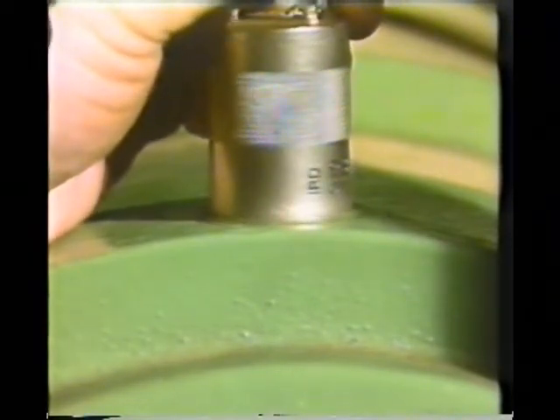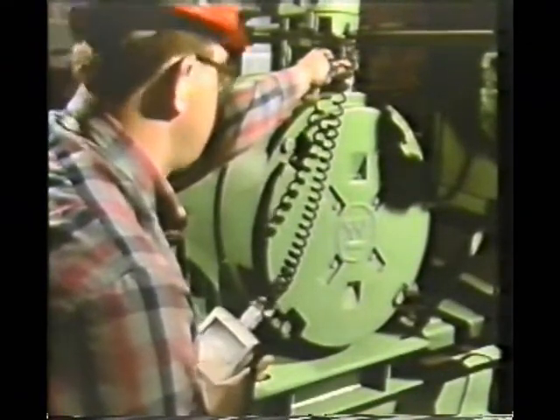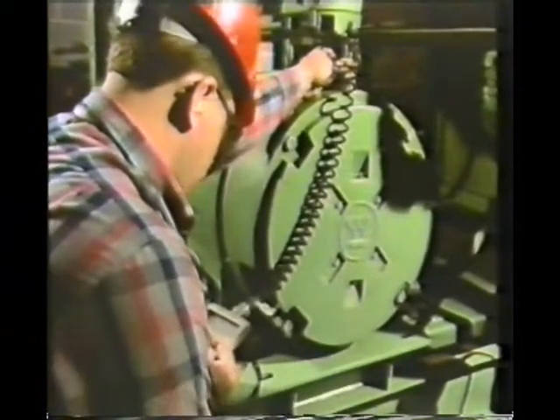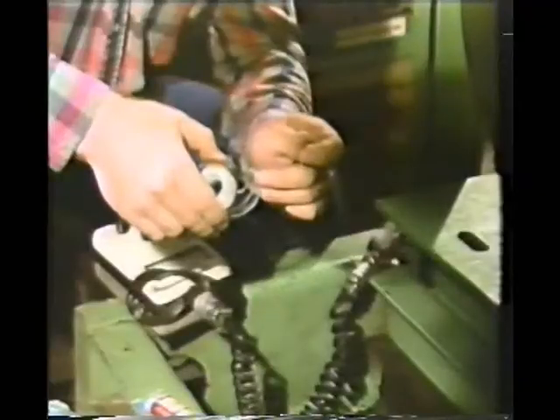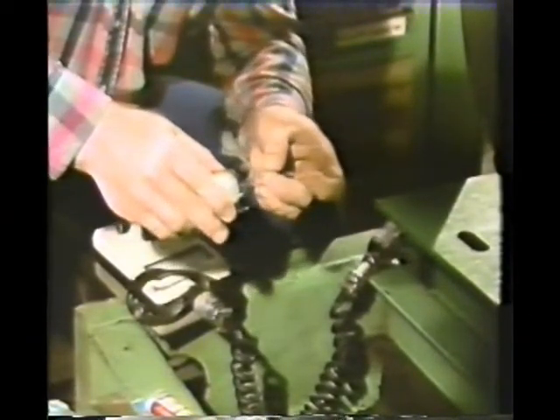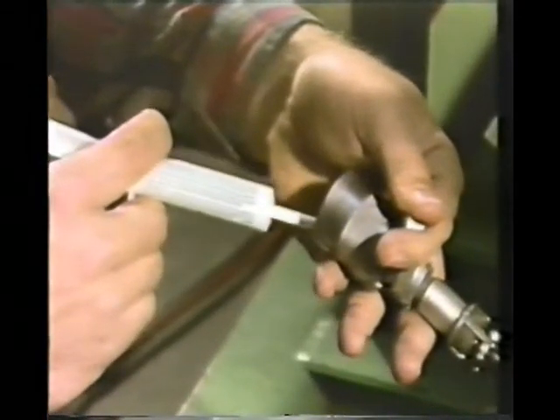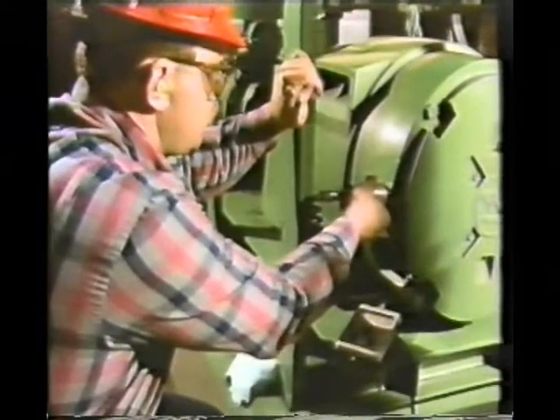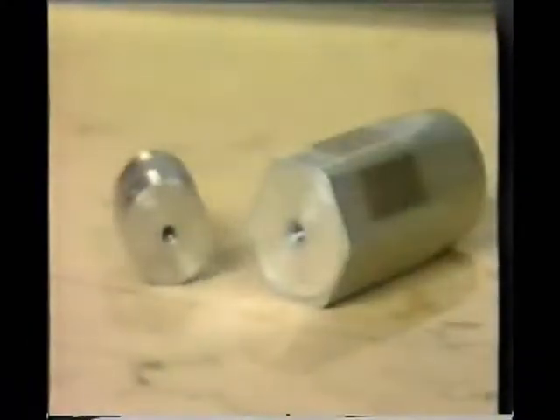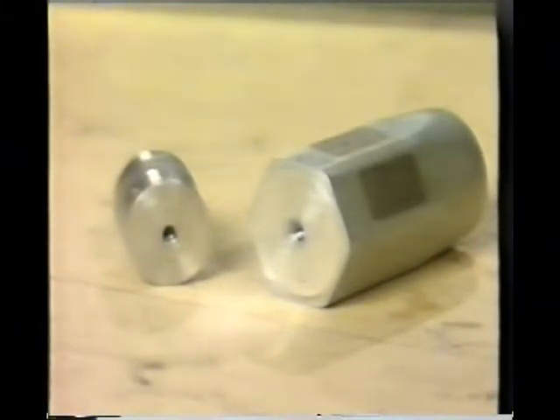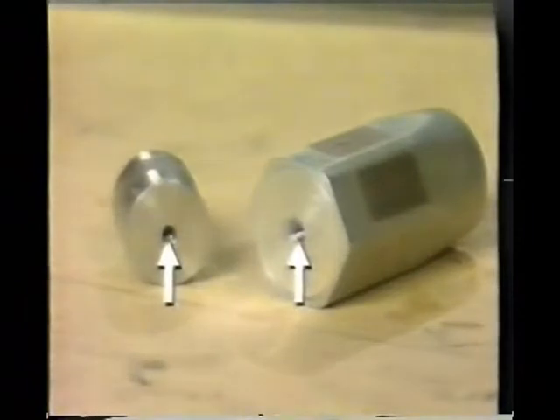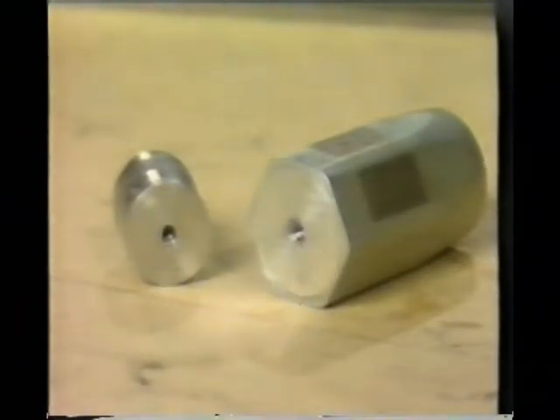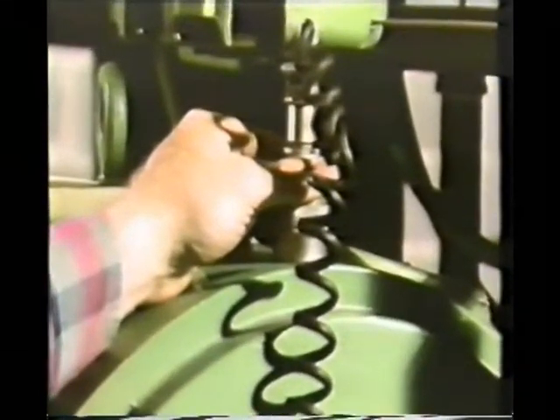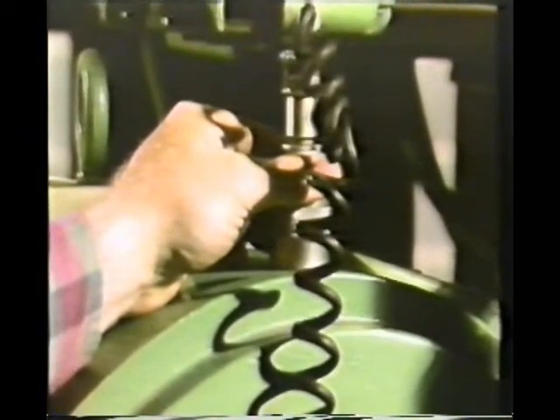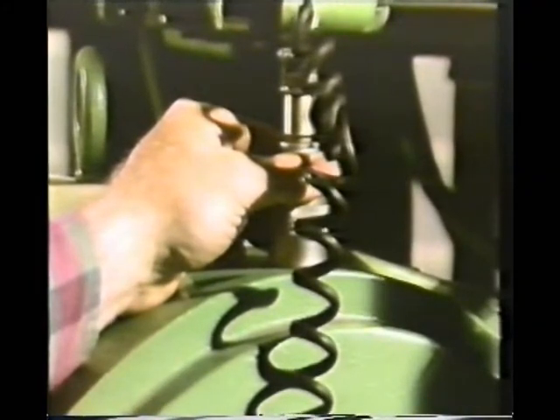There are a variety of ways to mount pickups. Determining which method to use could depend on the type of machine being checked. For example, the pickup can simply be held in place by hand, or it can be attached with beeswax or double-sided tape. A pickup can also be attached with glue or epoxy. Some pickup devices are equipped with a small magnet that's used to hold them in place. One of the most successful mounting techniques involves bolting the pickup onto the machine being checked. Many pickups are designed with a threaded bolt hole just for this purpose. Unfortunately, nearly every mounting procedure has some limitations. For example, holding the pickup in place can prevent the accurate measurement of higher frequency vibrations, and bolting the pickup onto the machine can be time-consuming.